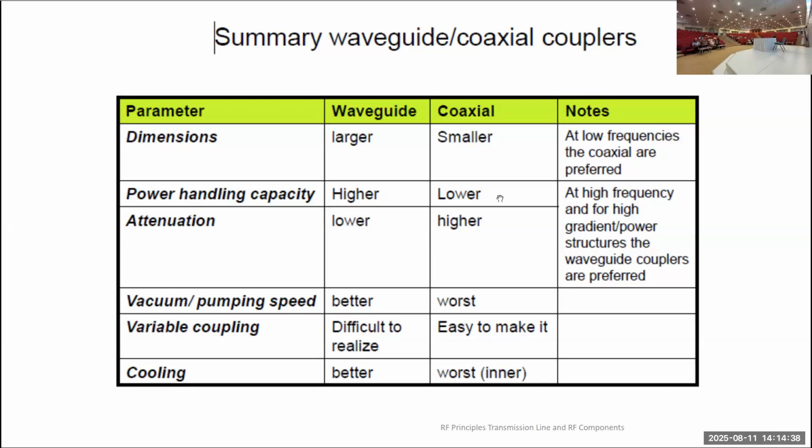Moreover, you can easily cool the waveguide components, but it is very hard to cool the coaxial coupling and coaxial waveguides, the coaxial transmission assembly.